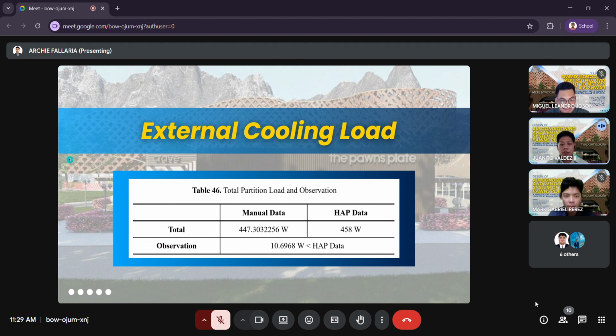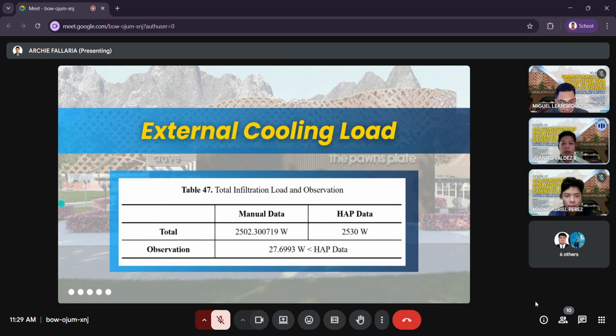Next, for the infiltration load. The infiltration load table captures the heat gain due to uncontrolled air entering the building through gaps, doors, and other openings. This is divided into sensible and latent heat gains, calculated from air exchange rates, temperature difference, and humidity ratio. The manual computation yielded a total load of 2,502.30 watts, while the HAP data yielded 2,530 watts, with a load difference of 27.70 watts.